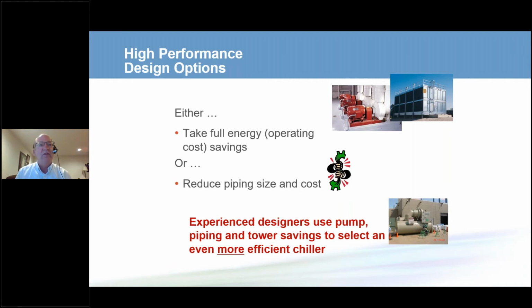There's a consulting engineer who wrote some articles on this a number of years ago, and they said they used some of the pipe, pump, and cooling tower savings to purchase a more efficient chiller. Because in the previous slides I've shared, we've used the same chiller. When we use some of the pipe costs, tower costs, and pump costs to put more money into that chiller, to put more copper, more heat transfer surface into that chiller, the difference between the old flow rates and the GreenGuide flow rates, the difference in chiller power, gets reduced. So there are a lot of different analyses we can make in order to apply this on particular jobs.